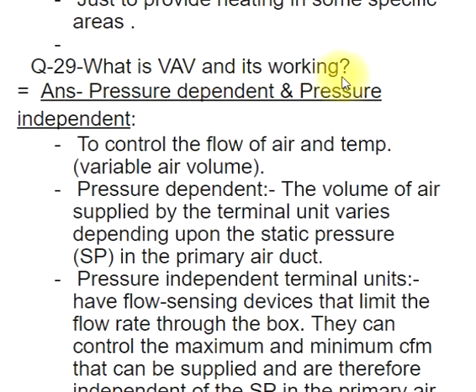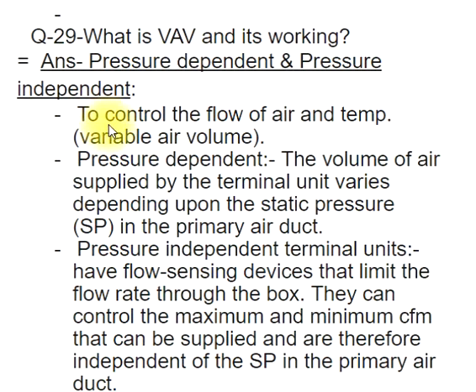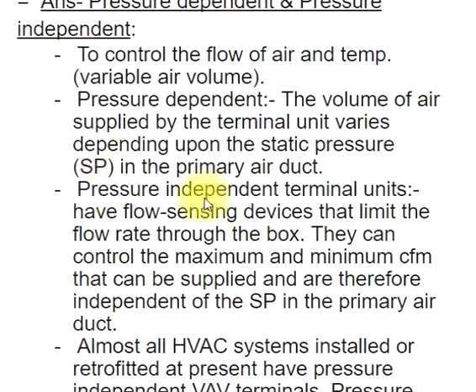Q29: What is VAV and its working? ANS: Pressure dependent and pressure independent. Used to control the flow of air and temperature — variable air volume. Pressure dependent: the volume of air supplied by the terminal unit varies depending upon the static pressure (SP) in the primary air duct. Pressure independent: terminal units have flow sensing devices that limit the flow rate through the box.